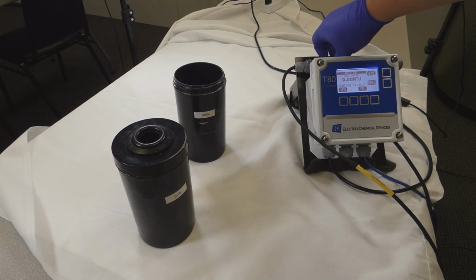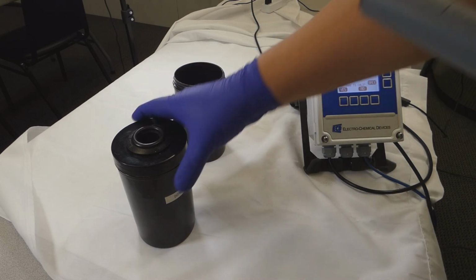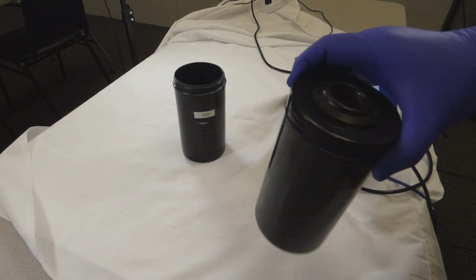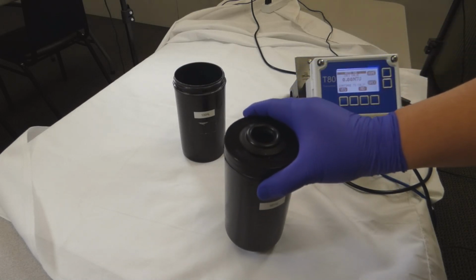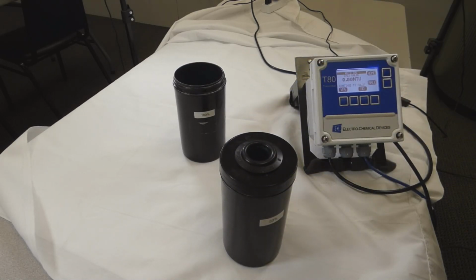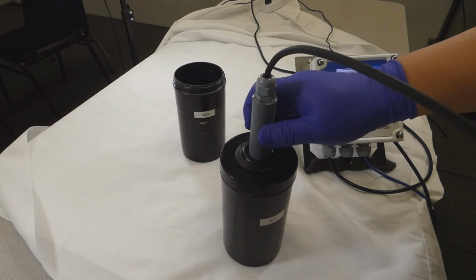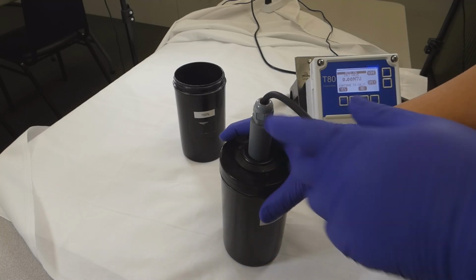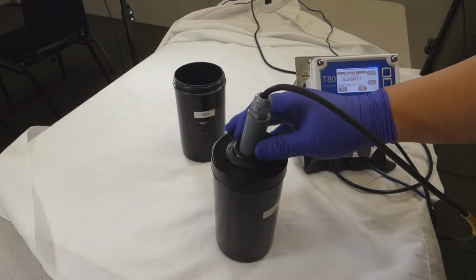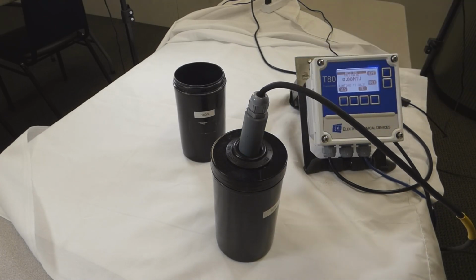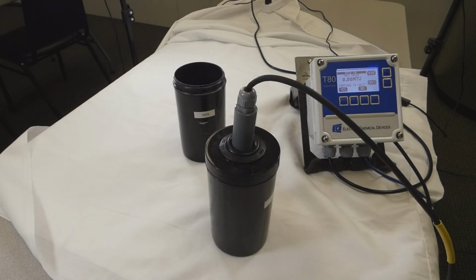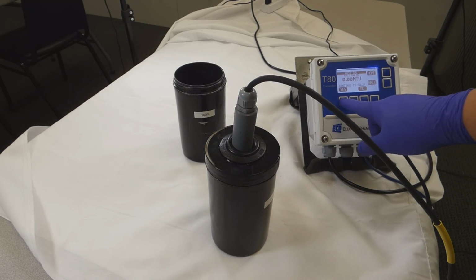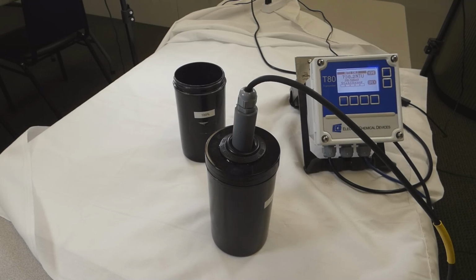You'll place the sensor now in your Cal 2 solution. You want to pick a dark container with no light reflection. This will be our 20 NTU solution. You'll let it sit here for about 2 to 3 minutes before moving on. Okay, now after the 2 to 3 minutes, you can move on to Cal 2 and wait for the stabilization bar to finalize.